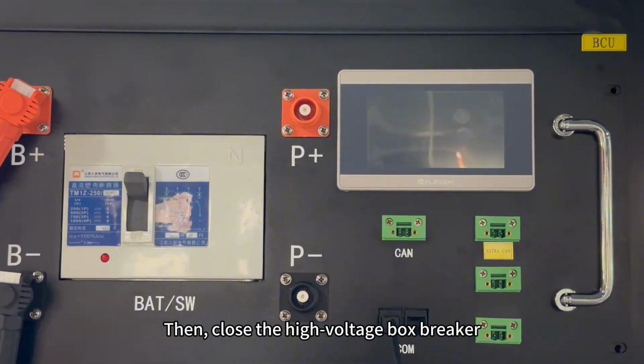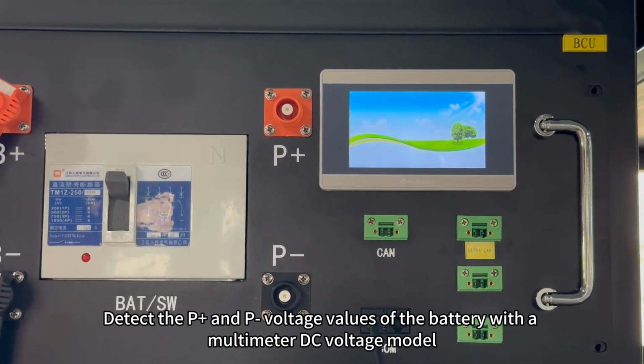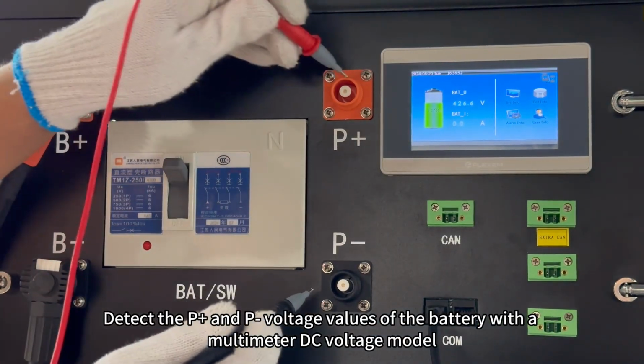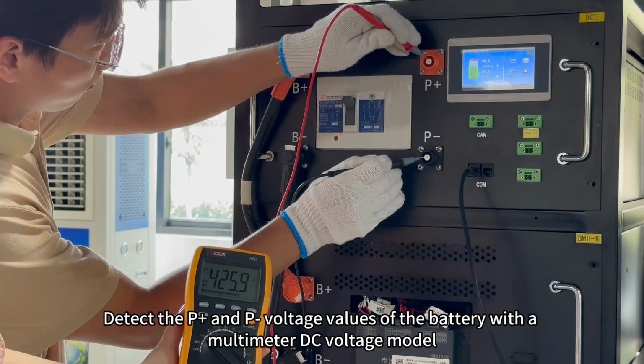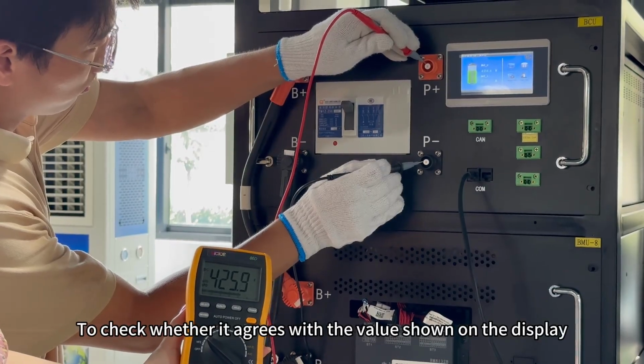Then close the high voltage box breaker. Detect the P+ and P- voltage values of the battery with a multimeter in DC voltage mode to check whether it agrees with the value shown on the display.